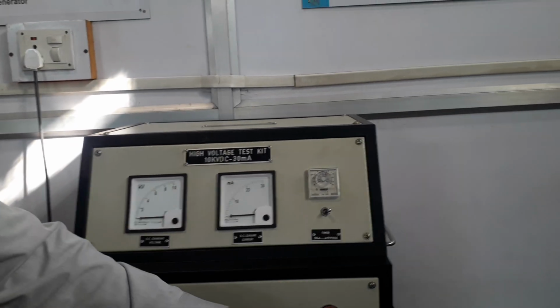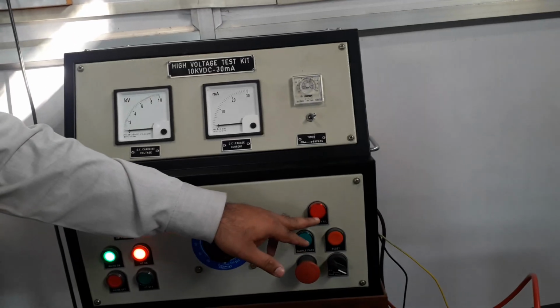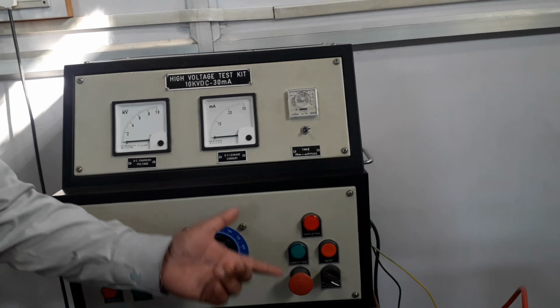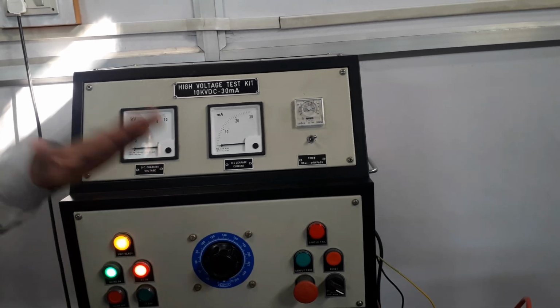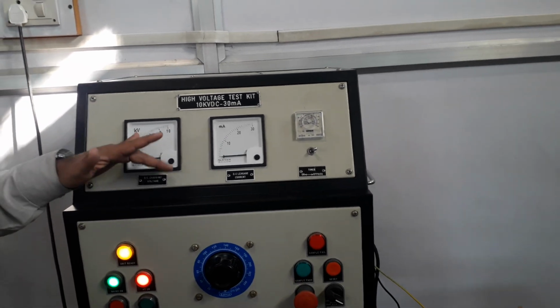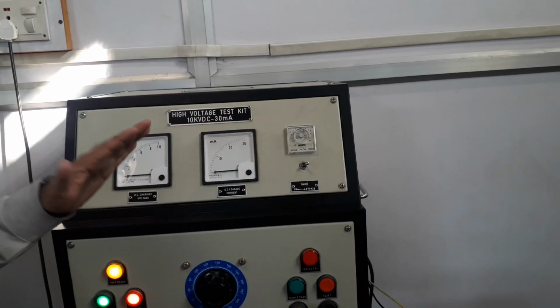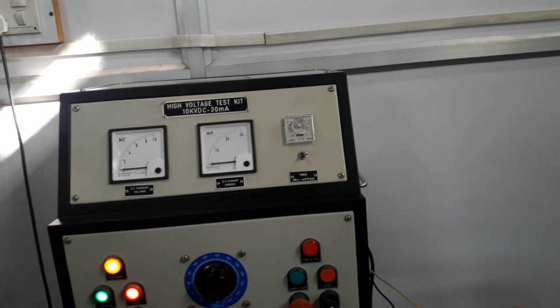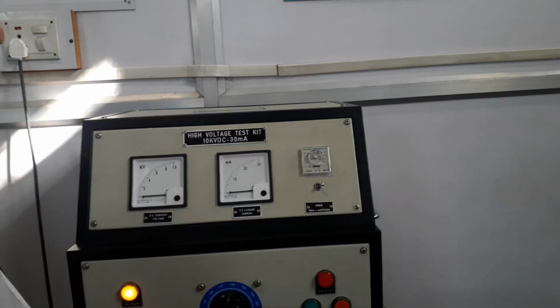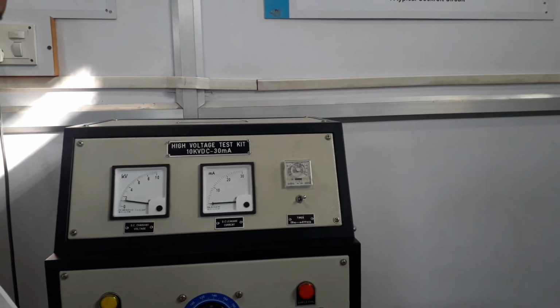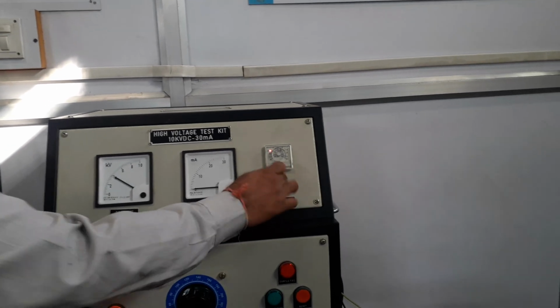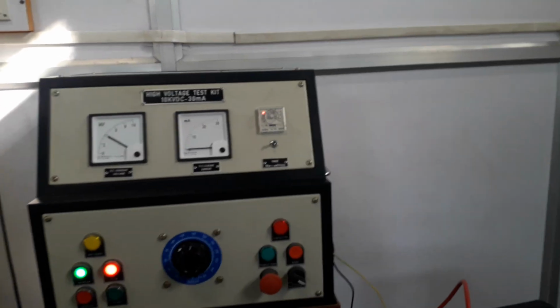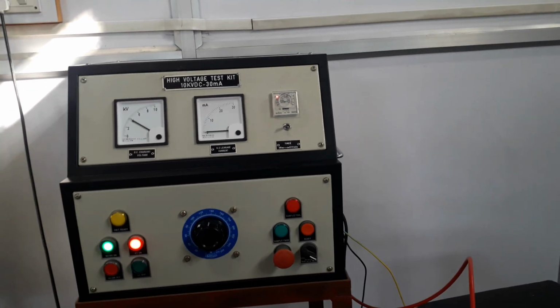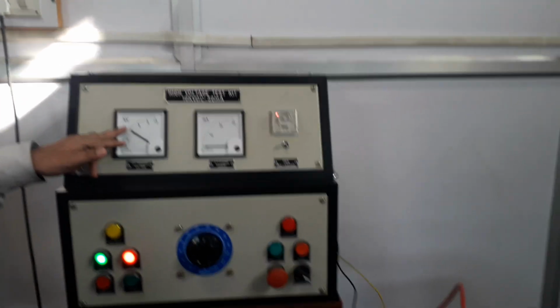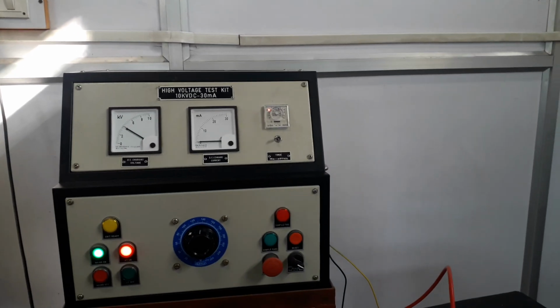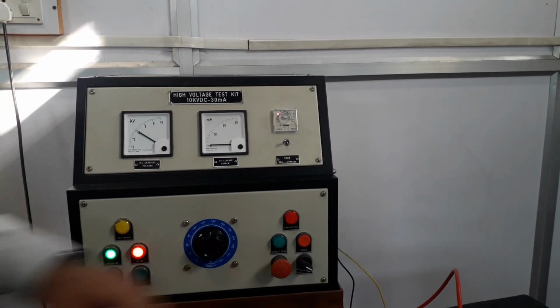If the sample fails within 6 seconds, then the sample fail indication will glow. If the sample passes the test and is able to withstand the particular voltage, for example 4 kilovolts for 6 seconds, then the sample pass indication will glow. So now we will set up the voltage first, then we will switch on the timer. We will wait for some time, and if the sample withstands the applied high voltage for the particular amount of time, then the sample pass indication will glow.